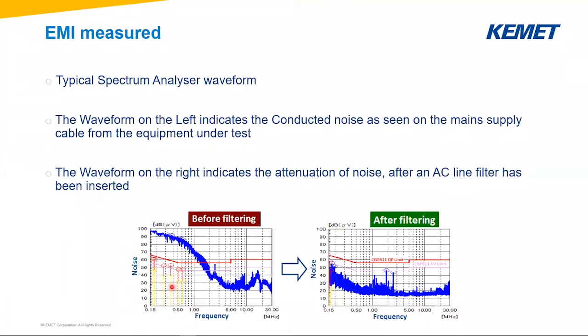After testing, you receive a typical spectrum analyzer waveform. On the left you can see conducted noise — for example, from a mains supply cable. The red line is the limit and the blue curve is the measurement result. If the blue curve exceeds the red line, you fail the test and need to change your design. In an ideal world, after filtering with good components — either common mode chokes or X/Y capacitors — you will pass, and that's where we want to go today.